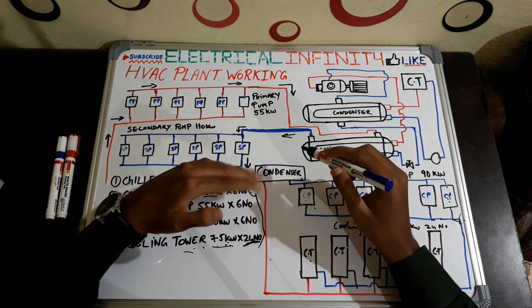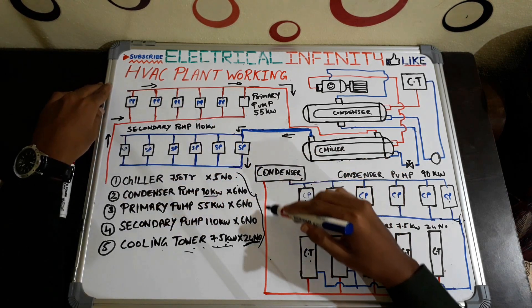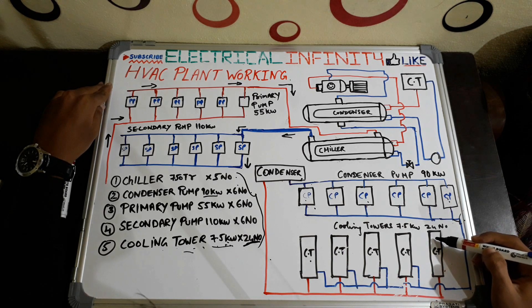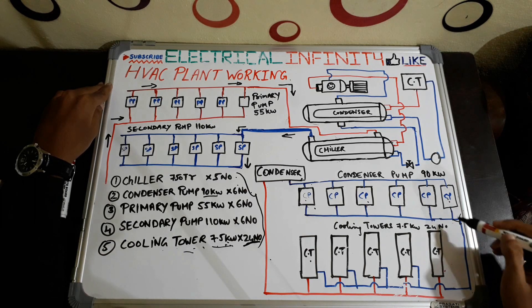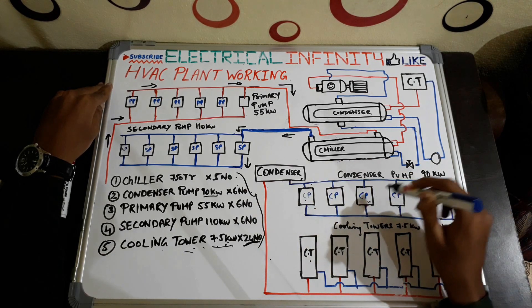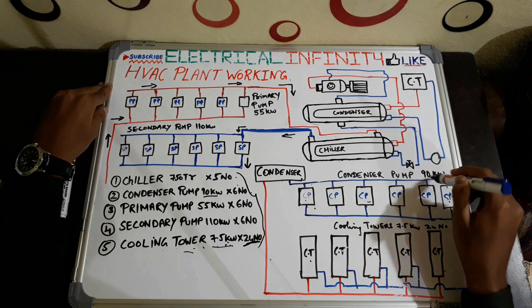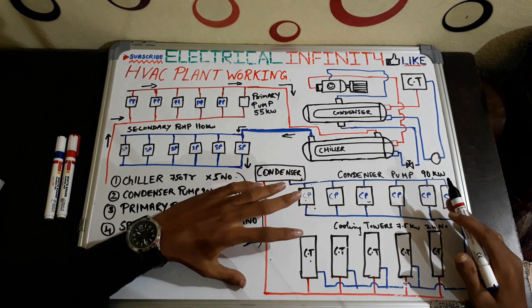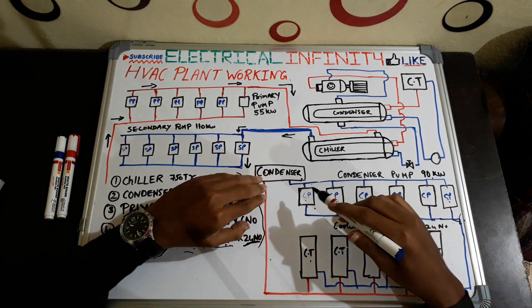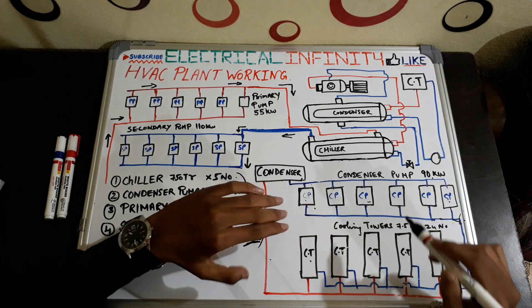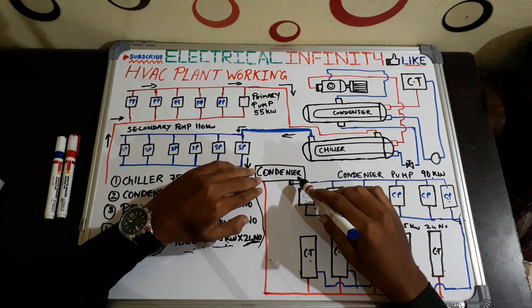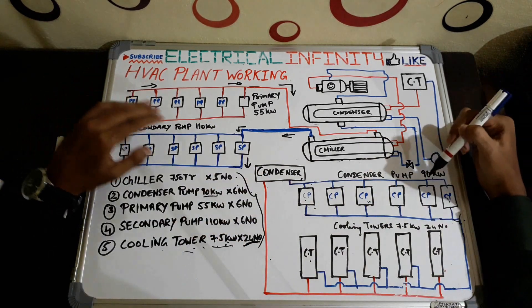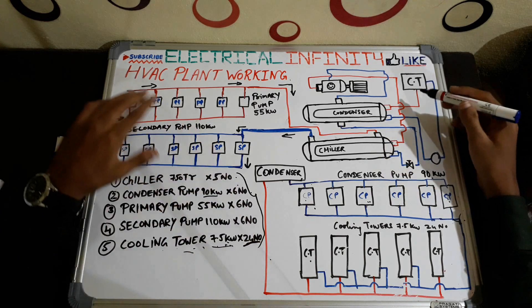After the heat exchange, the water gets heated up and the refrigerant gets cooled. The heated water is again transferred to the cooling tower where it is cooled down. This cool water is then transferred back to the condenser with the help of the condenser pumps — each pump is 90 kilowatt and we have six condenser pumps. So this is the setup for cooling the refrigerant in the condenser using the cooling tower and condenser pumps.